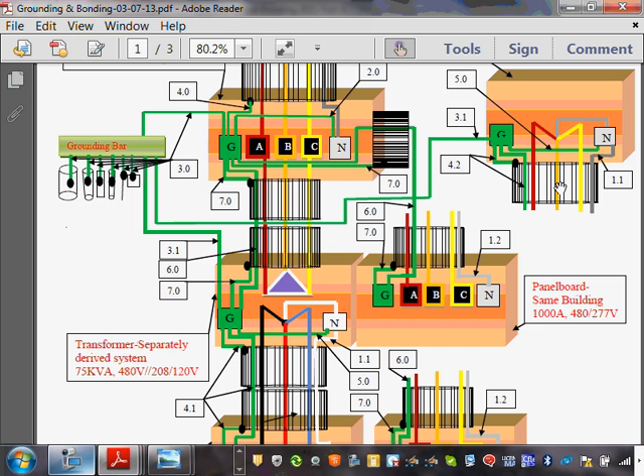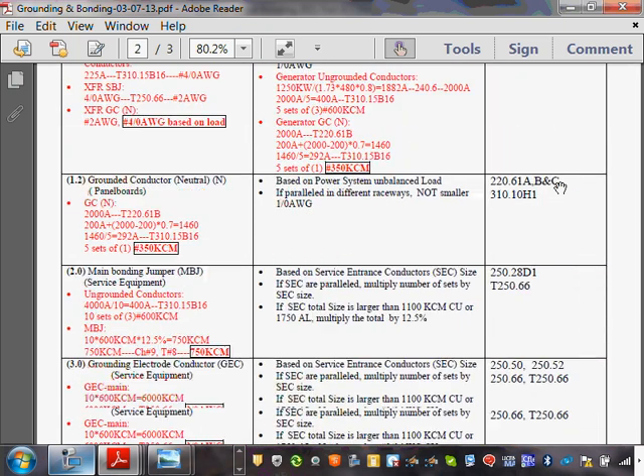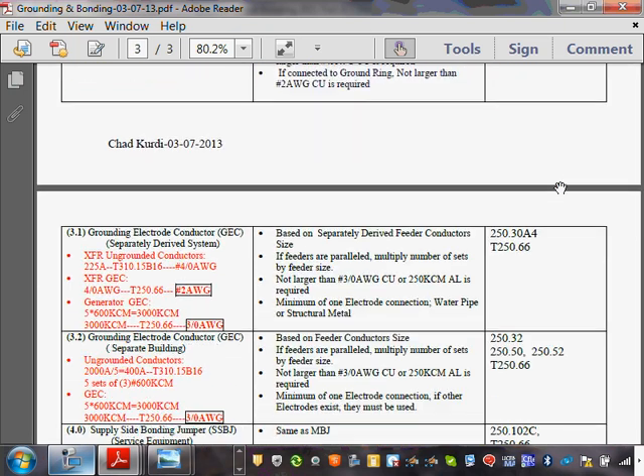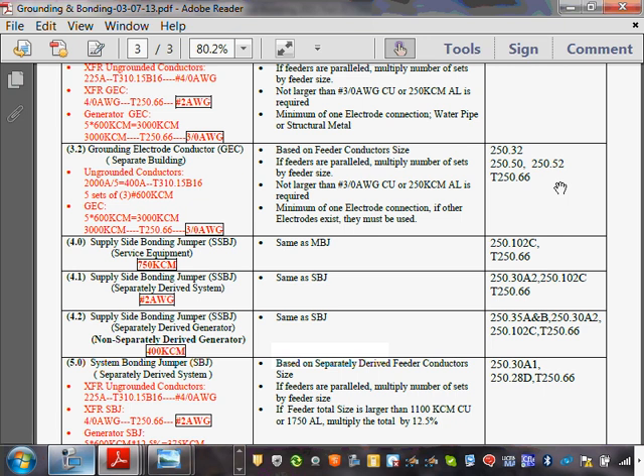If the circuit breaker is right inside the switchgear, and I'm pulling just a feeder between the two, like we do in bigger systems with parallel switchgear, then this conductor is called a supply side bonding jumper. So let's do it as a supply side bonding jumper, guys, 4.2. Here's my 4.2, a supply side bonding jumper, separately derived system. Exactly, you size it the same as the system bonding jumper, 400 kcmil. Is that what the 4.2 says?